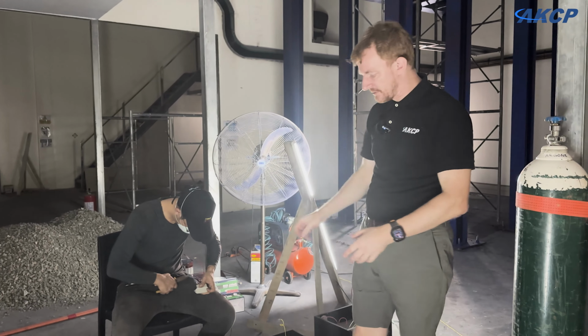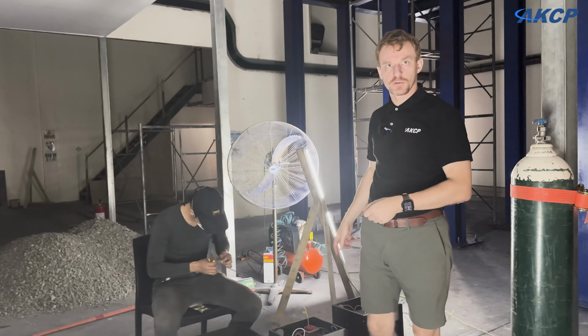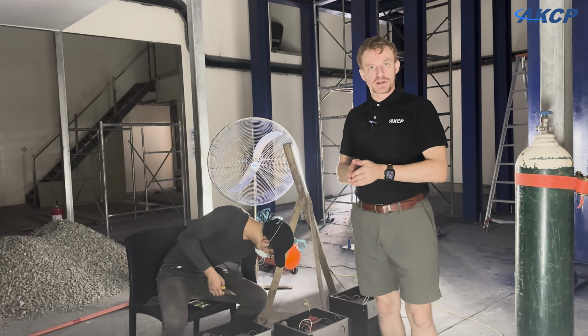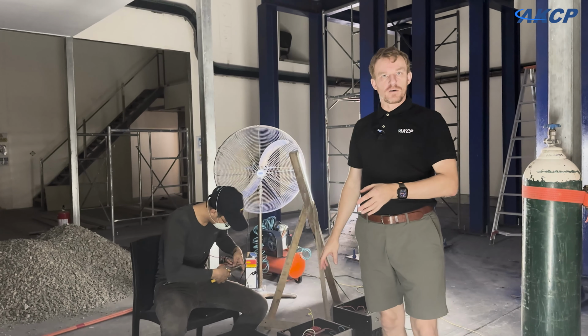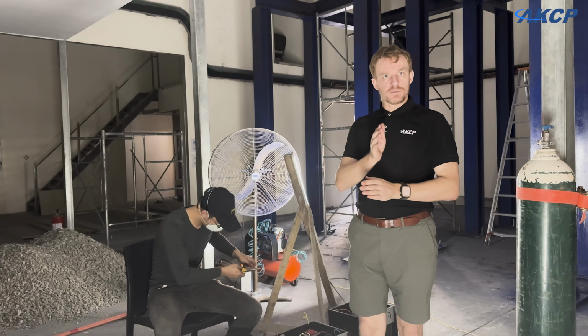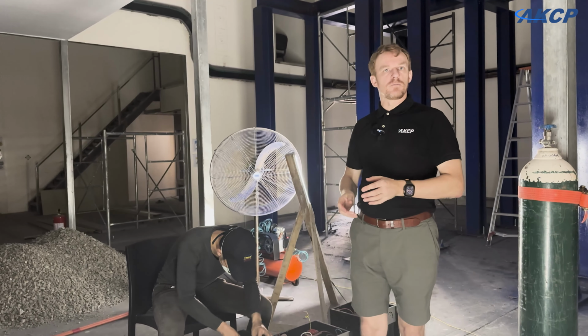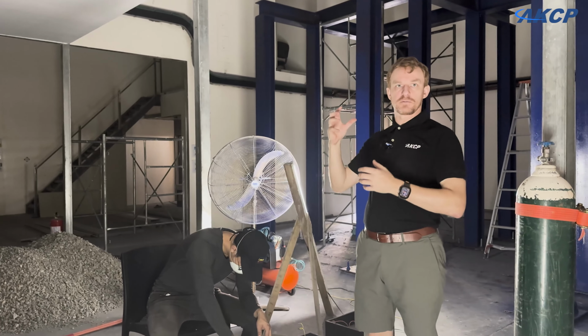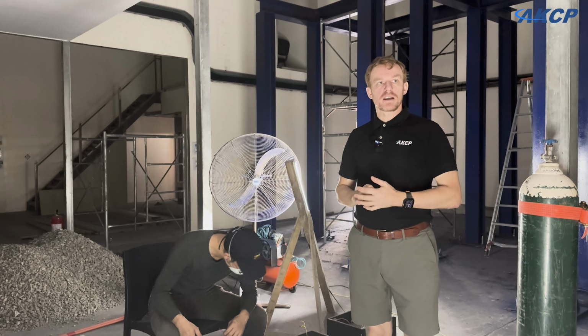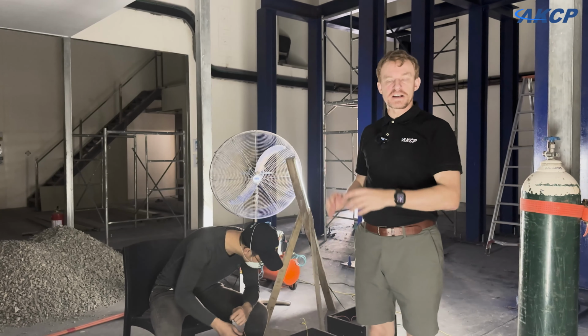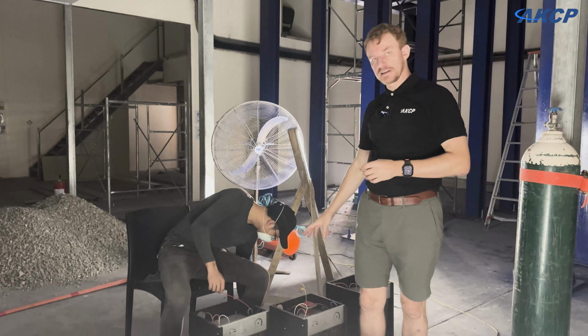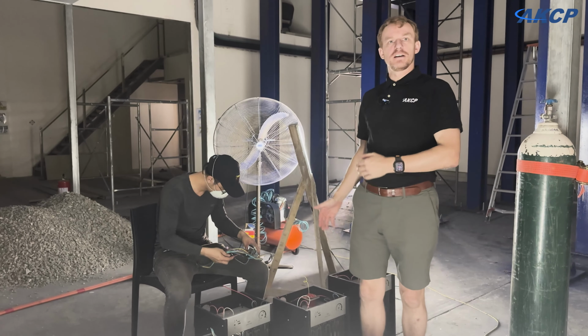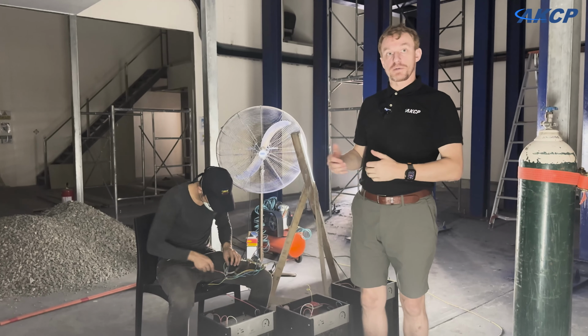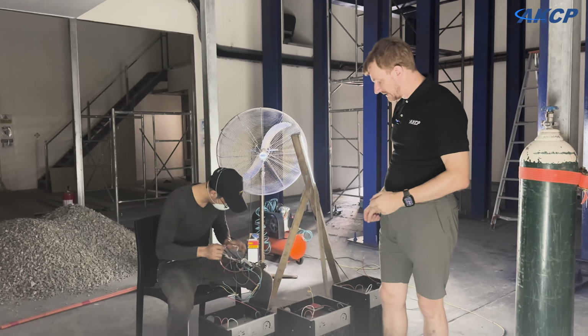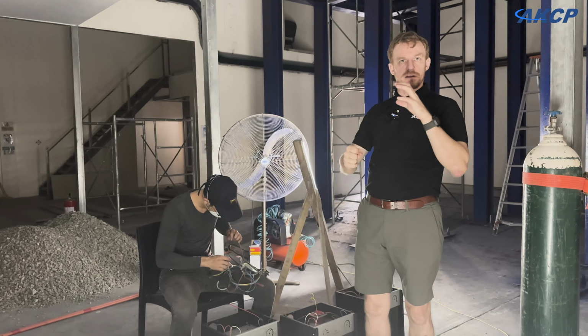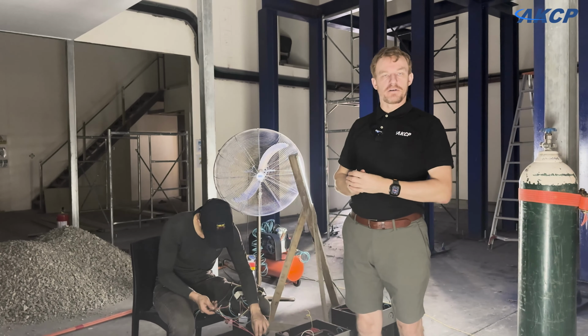What we're currently doing here is rewiring these to make them into single phase. So rather than bringing 3-phase in and splitting it into 3 individual phases internally, we're going to wire up all of the individual heating elements in parallel, and then connect them to a single phase, because the breakout box that we have on our overhead power distribution has 3 single phase outlets, and we have 3 heaters. Each one of those outlets can handle 20 amps. So 3 of the elements inside one of the heaters is around 15 amps, so we won't be tripping the breakers. That's what we're doing at the moment, rewiring these, and we'll bring out a single cable with a single phase socket on the end that we can plug in to the overhead power distribution.